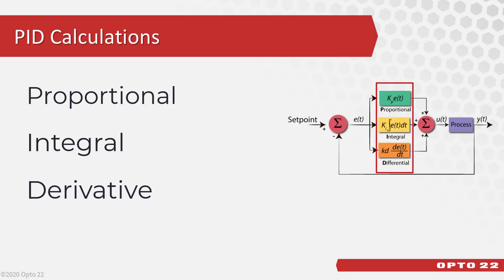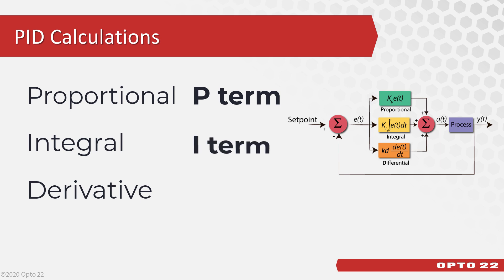The calculations done by the PID algorithm are referred to as the modes of control: the proportional (P term), the integral (I term), and the derivative (D term). How much each term influences the output is determined by the P, I, and D tuning constants — values that you'll enter to tune your PID.